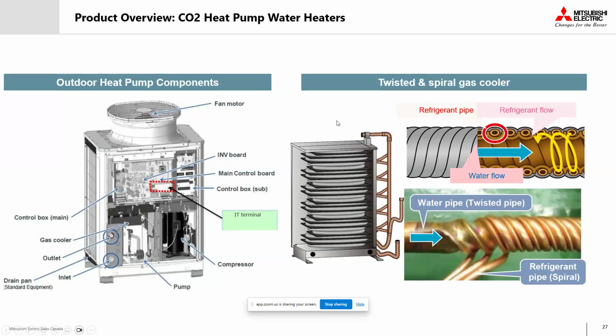Just to take a quick walk through the core components of a high lift CO2 heat pump water heater, what you would see here is a monoblock QAHV model offered from Mitsubishi Electric. Within this chassis, we're housing all of the common heat pump elements, like the inverter-driven compressor, outdoor coil, as well as an internal circulating pump for the primary fluid loop.